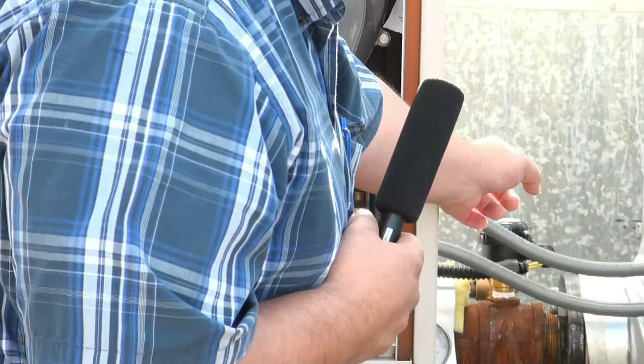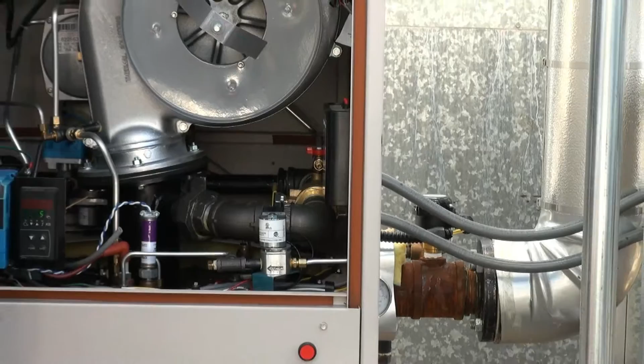The other safety is a flow switch that's sitting on that pipe right there. They're going to rewire it on Monday. It's just a wiring issue. That makes sure the pump's on. If the pump's not on, there's no flow to the tower, and it's going to trip it off. The last one is the high temperature, which is sitting right here. It pops up, and you just have to reset it.